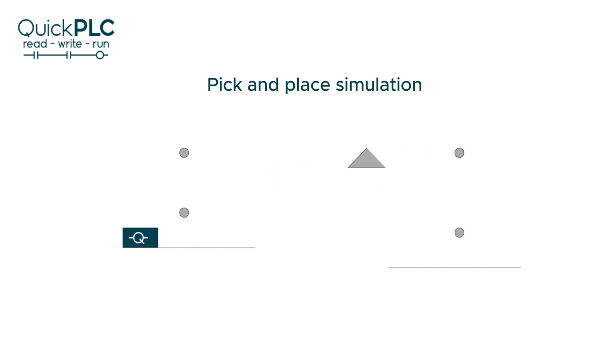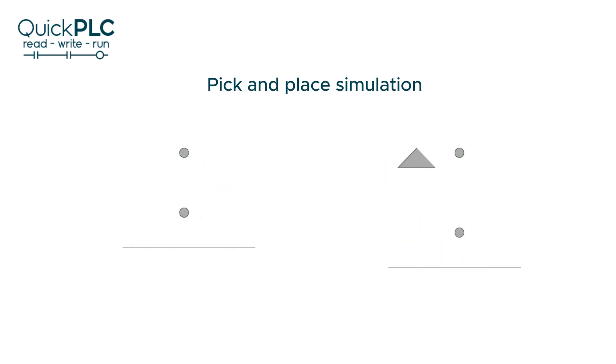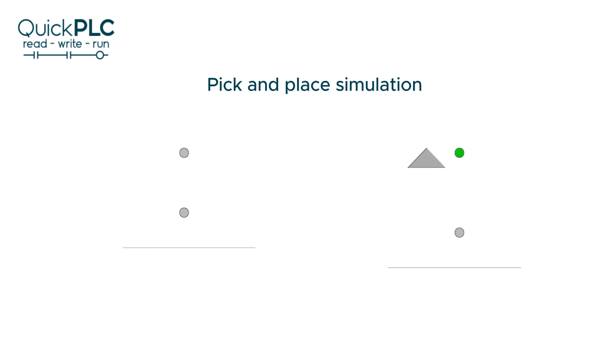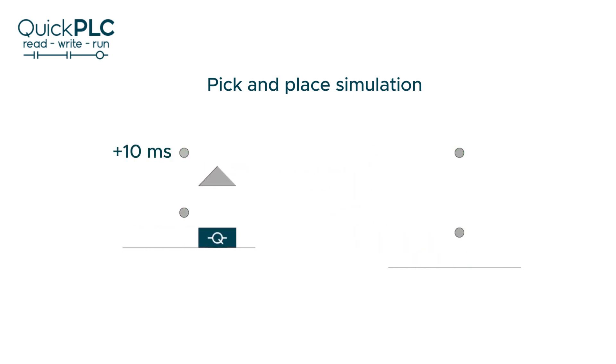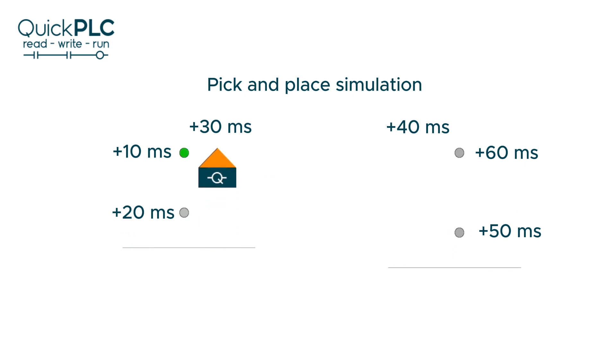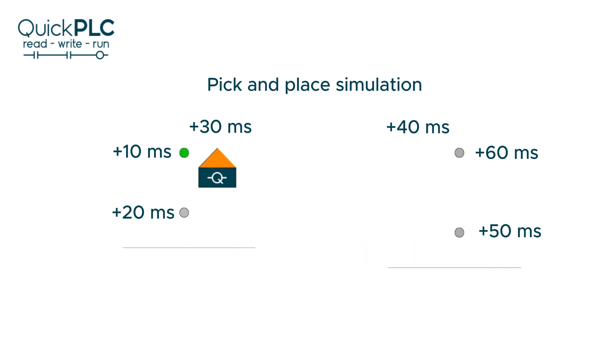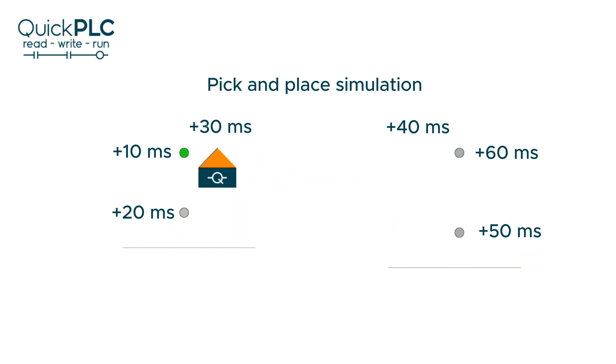For example, in this animation the pick and place cycle is about 3 seconds. In one cycle there are 6 position sensor checks. If the PLC scan time was 10 milliseconds, then there's potential for 6 times 10 milliseconds variation in the cycle time which works out to be 60 milliseconds or 2%. By halving the scan time we could reduce the variation and improve the machine performance and possibly quality as well if timing is critical to the process.